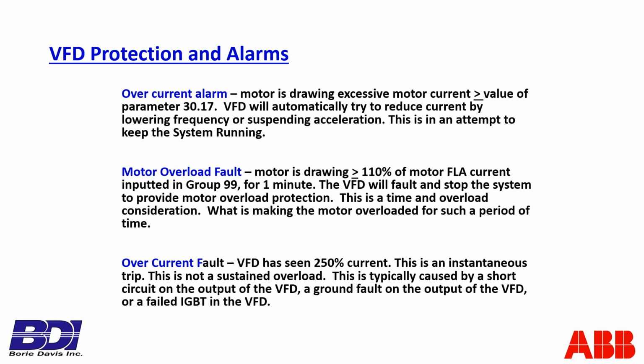Something's changed there. The overcurrent fault is an instantaneous trip saying the VFD just saw 250% current. This isn't like a motor overload. This is like a wire fell out from underneath a wire nut in the motor winding connection and just hit another phase or hit ground. You'd get an instantaneous high current, and that would cause that overcurrent fault. That fault is there to actually protect the IGBTs, the output semiconductors in the variable frequency drive. We're going to learn more about those later. But it is also something where you look at the output as a possibility of having caused that issue.